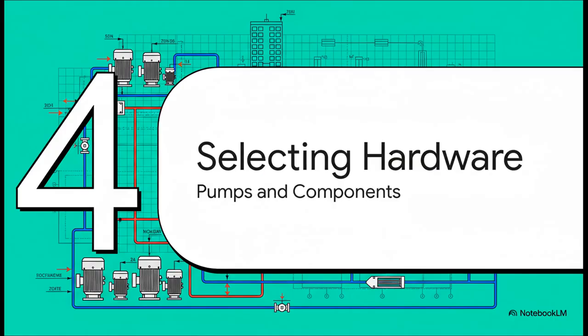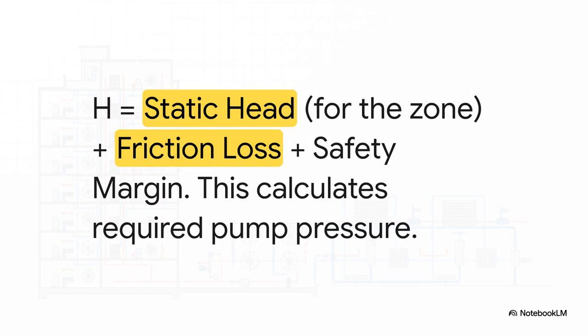So now that we have these neat independent zones, we can basically treat each one like it's its own smaller building. And what that means is we can finally select the right pumps for each specific job without worrying about insane pressures. To pick the right pump, the first thing we need is its head, which is just the amount of pressure it needs to create. And we calculate that by adding up the static head for that zone only, plus the friction loss you get from water moving through pipes, plus a little extra for a safety margin.